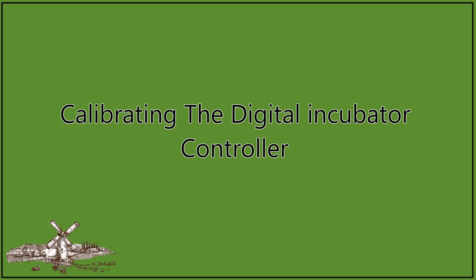So in this week's video, I'm going to talk about calibrating your digital incubator controller. And I'm going to start with this one because I've seen quite a few people online asking what calibration was, how calibration should be done, and what tools are required. I've also seen some people stating that their controllers don't require calibration because they are in fact self-calibrating. Now, I can assure you that no digital controller is self-calibrating. So if you are not calibrating your own controller, your controller is not reliable and it is not accurate, and that could possibly be what is to blame for a low hatch rate.